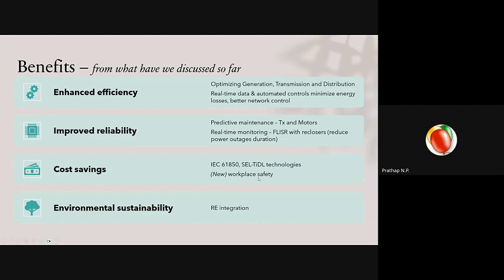Then there's workplace safety. In underground vaults—since in the city you don't usually see overhead conductors, distribution is mostly underground cables—you have vaults you go down into for maintenance. These underground vaults can produce hazardous, dangerous gas that can kill you if you breathe it. And second, if something is happening outside, you won't know—someone would have to radio or phone you to say stop work immediately and come outside. There needs to be some manual intervention there.